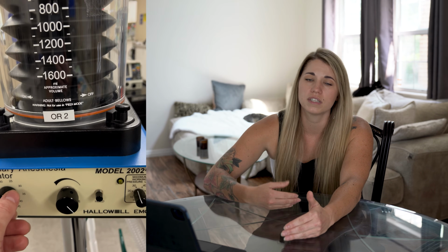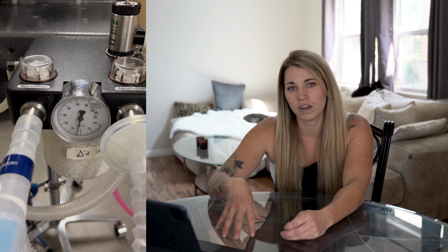Your ventilator will alarm if you have reached your maximum working pressure limit. Again, that is the pressure limit that you have set the ventilator to not exceed. When a ventilator has hit its maximum working pressure limit, it'll flash yellow and it'll stop delivering the breath. To remedy this, you need to either decrease your volume, or, as I just stated, you may need to try to catch your patient's respiratory cycle by increasing the anesthetic depth or increasing the respiratory rate of the ventilator.